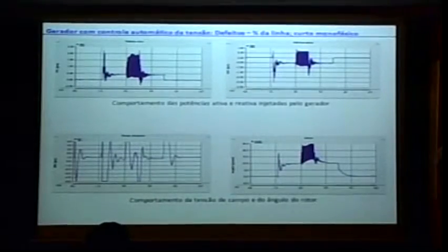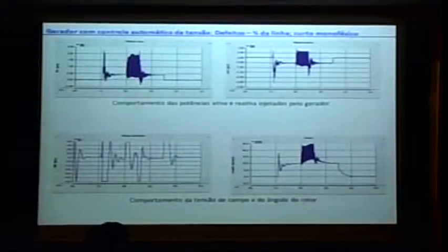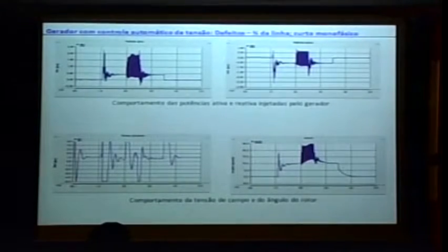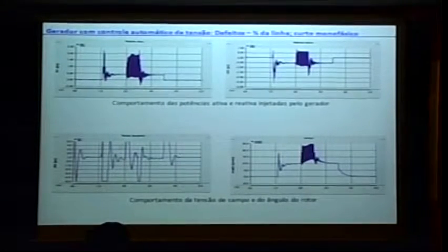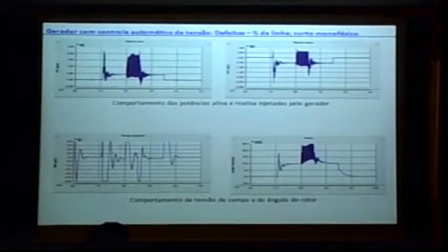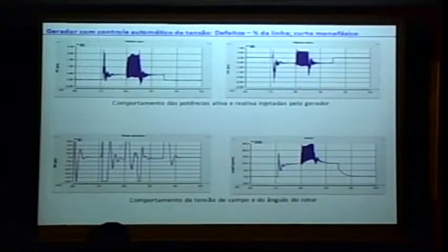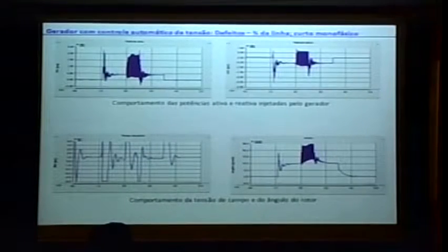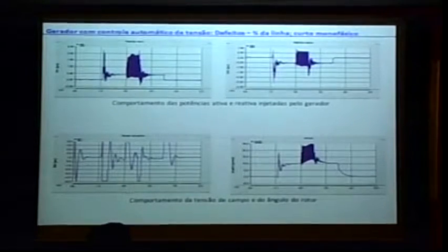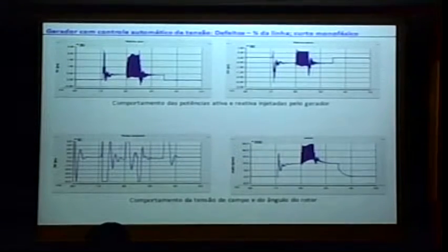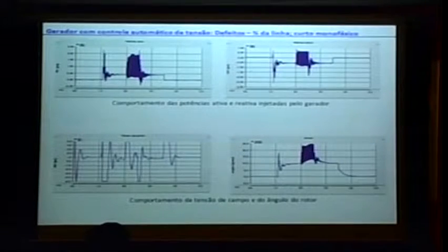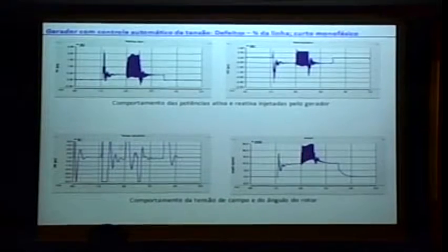Something different occurred here in the single-phase short circuit upon the generator. It continued providing a high quantity of reactive power, around 2 pu, during the whole existence of the short circuit. So it provided 2 pu of reactive power and more than 1 pu of active power sustainably until the short circuit was eliminated. That had not happened before in the three-phase short circuit. This shows the behavior of the AVR, and here is the load angle. The load angle was also oscillating during the whole existence of the short circuit.